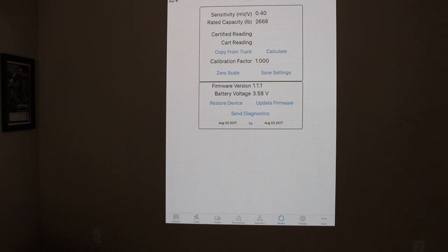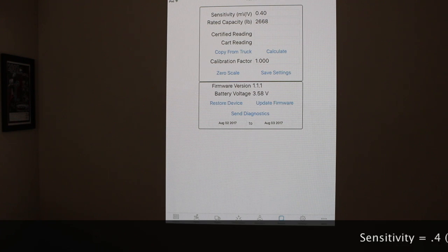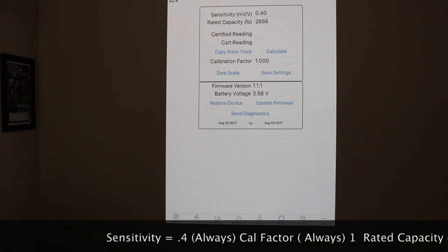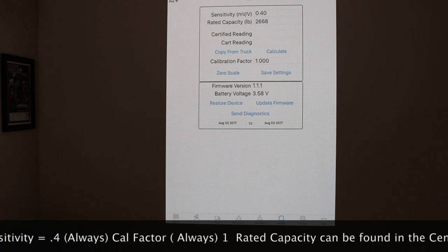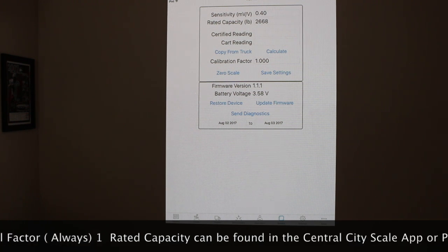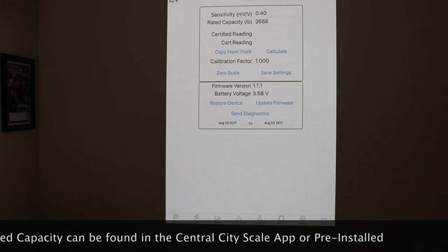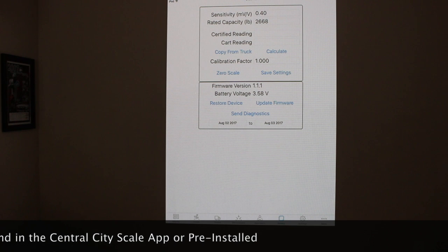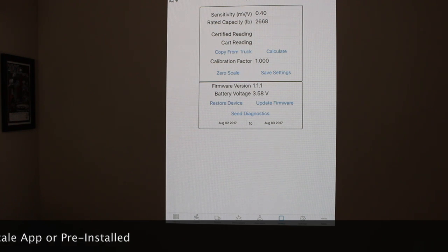Problem is that the rated capacity doesn't always coordinate with sensitivity because the sensitivity will change as the weight increases. So to counterbalance that, I like to use the sensitivity of 0.4 and then have a calibration factor of 1. And I can't stress this enough, have the sensitivity always at 0.4, do not deviate from that. And then leave your calibration at 1, do not deviate from that. And then this process will be rather simple because it's just like a basic scale head how we calibrate it then. The rated capacity is no longer a rated capacity in those terms, it just becomes a cal number.